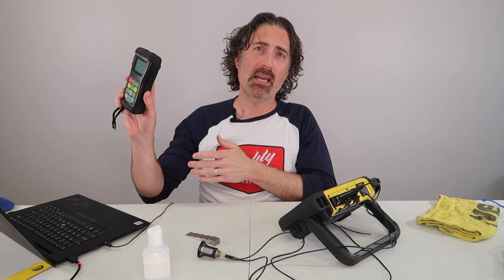V-path error is not really a problem if you've got a thickness gauge like that. You plug the probe in, it knows what's going on, it'll fix everything for you. If you don't, and you're doing thickness testing through flaw detectors, which I know a lot of people do, then it's really, really important to pick your calibration points very close to what you're trying to measure.